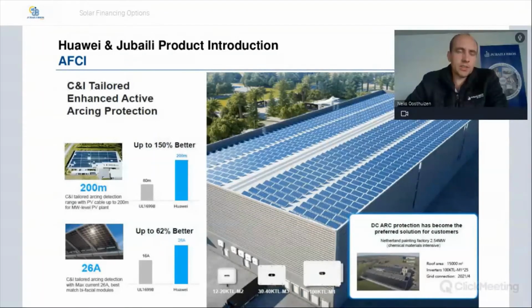Then the next feature is the AFCI. What is it? It's arc fault circuit interruption. On this slide, we're focusing specifically on the standard. The standard used for AFCI is the UL 1699B standard, which says that arc fault circuit interruption should be able to detect up to a distance of 80 meters, but Huawei is able to detect up to 200 meters. Then again, the standard is specified at 16 amp. The Huawei can detect even on a 26 amp circuit.